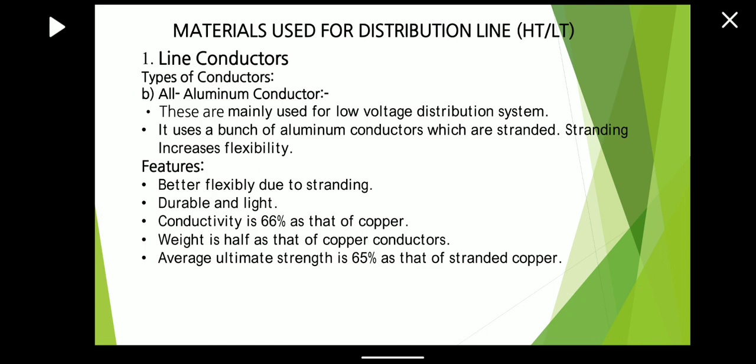The second type of conductor is the All Aluminium Conductor, also called AAC. These are mainly used for the low voltage distribution system. It uses a bunch of aluminium conductors which are stranded. Stranding increases flexibility. Features of AAC: better flexibility due to stranding, durable and light. Conductivity is 66% that of copper. Weight is half that of the copper conductor. Average ultimate strength is 65% that of stranded copper.